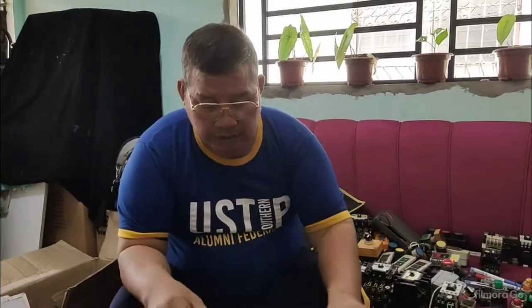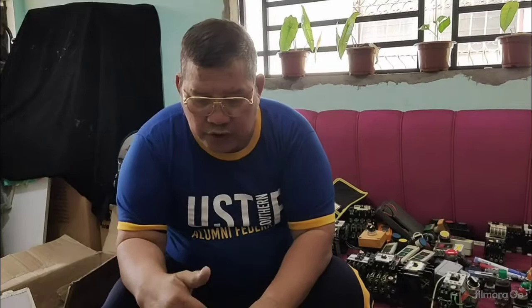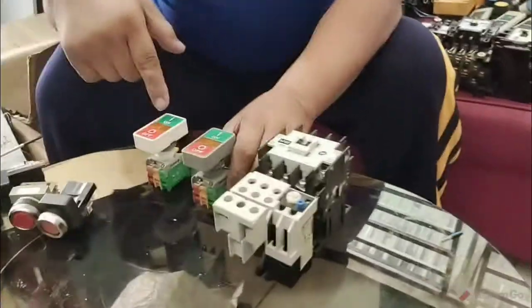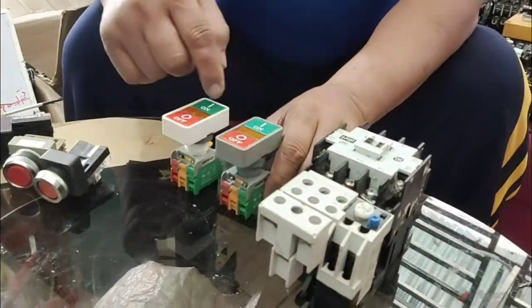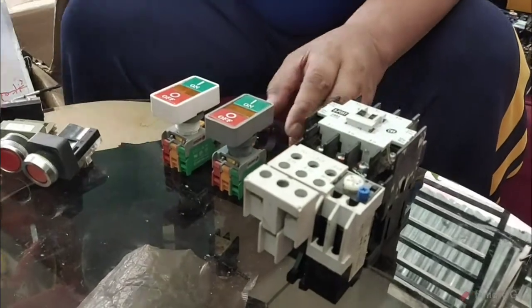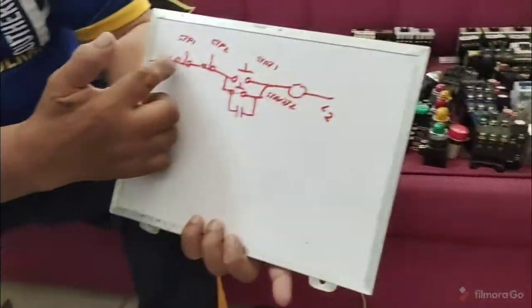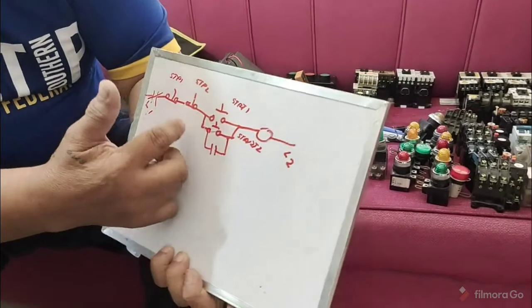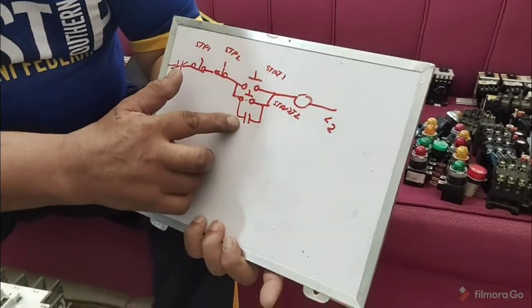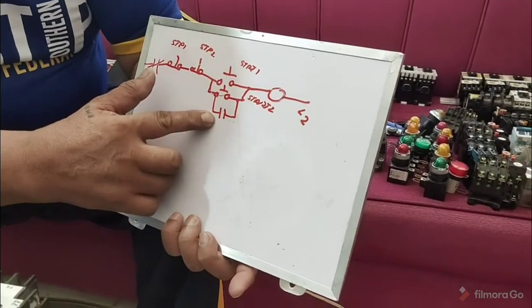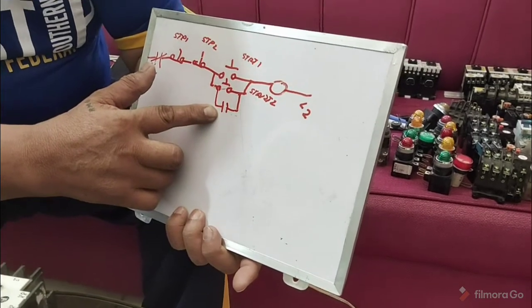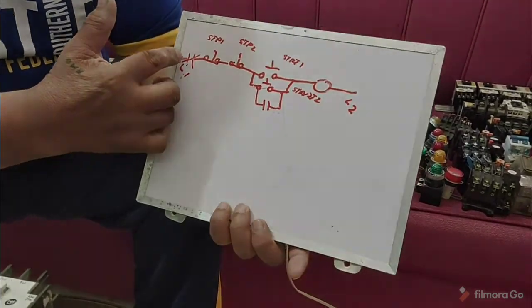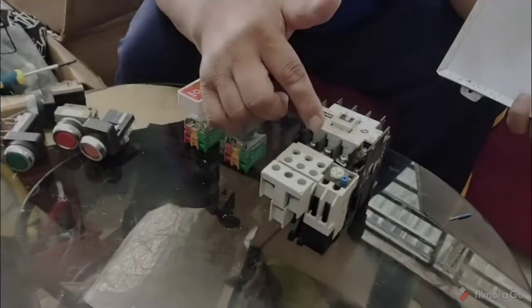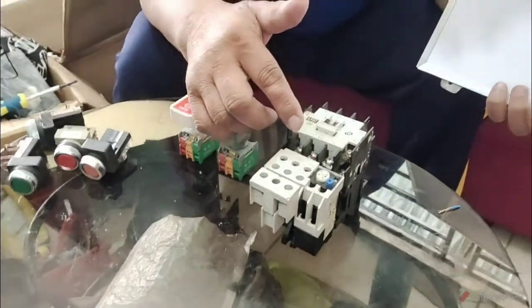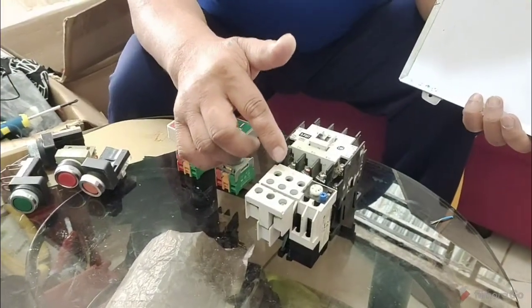Now, as I illustrated, if that is normally closed, you connect it in series. If that is normally open, or an on button, you connect it in parallel. So you have a stop button and a start button, and you will use only one holding circuit or maintaining contact, plus an overload contact. It's still working, so that is it.